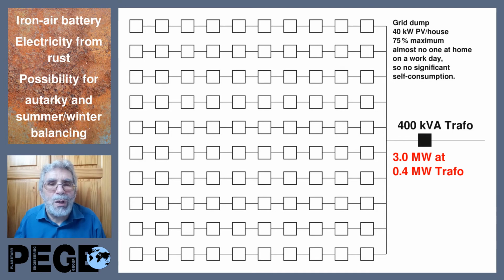We are talking here about climate protection superior houses, and they have very much photovoltaic. Let's have here only an average of 40 kilowatt photovoltaic per house. And when they would all dump the electricity from the photovoltaic directly to the grid, this could be 3 megawatt, about 75% of the maximum, because it's east-west roofs, and so we have 75% of the theoretical maximum of the installed photovoltaic. Or we would have here a very massive necessity for a grid extension.